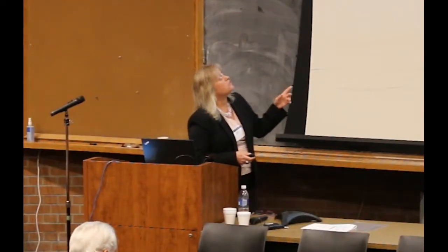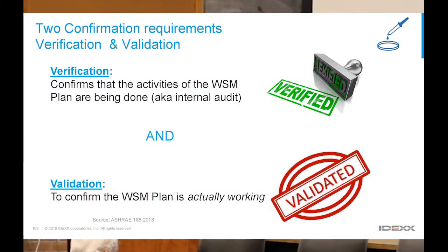So verification and validation are two different things, all right? Verification will confirm for you whether or not the activities of your plan are actually being done. So Patrick and Bill talked a lot about you identify what the hazard is, you put control measures in place, and then you monitor them, right? So we've talked about all that. What verification is, is rather like your internal audit. Did everybody do what they were supposed to do? And you have a little checklist. Validation is what you do to ensure that your plan is actually effective. Am I actually managing Legionella pneumophila in my system?